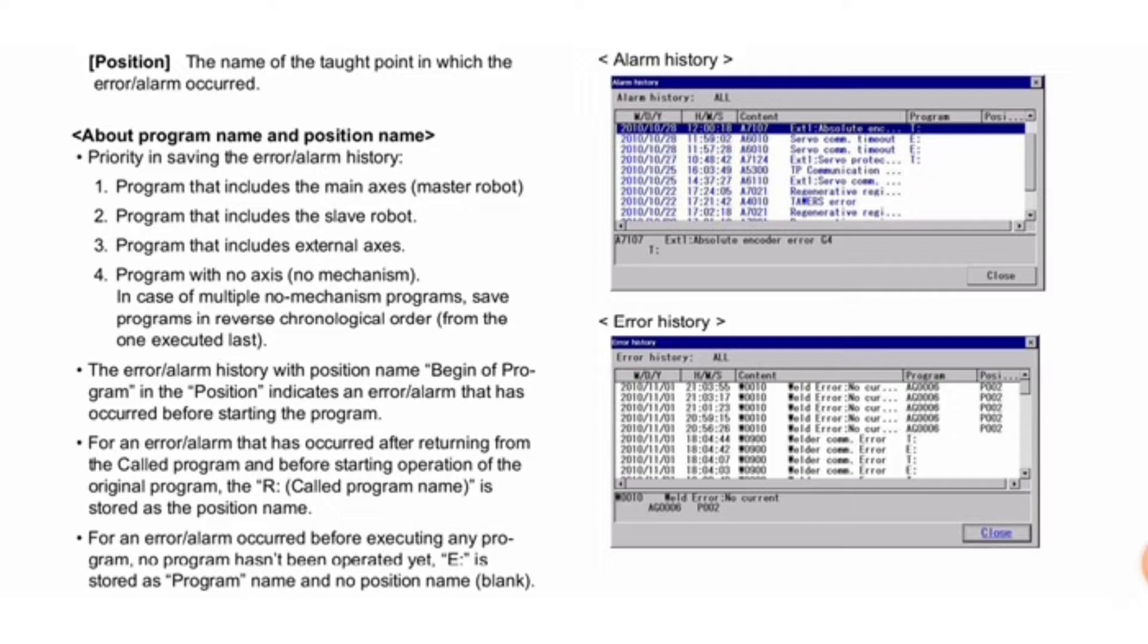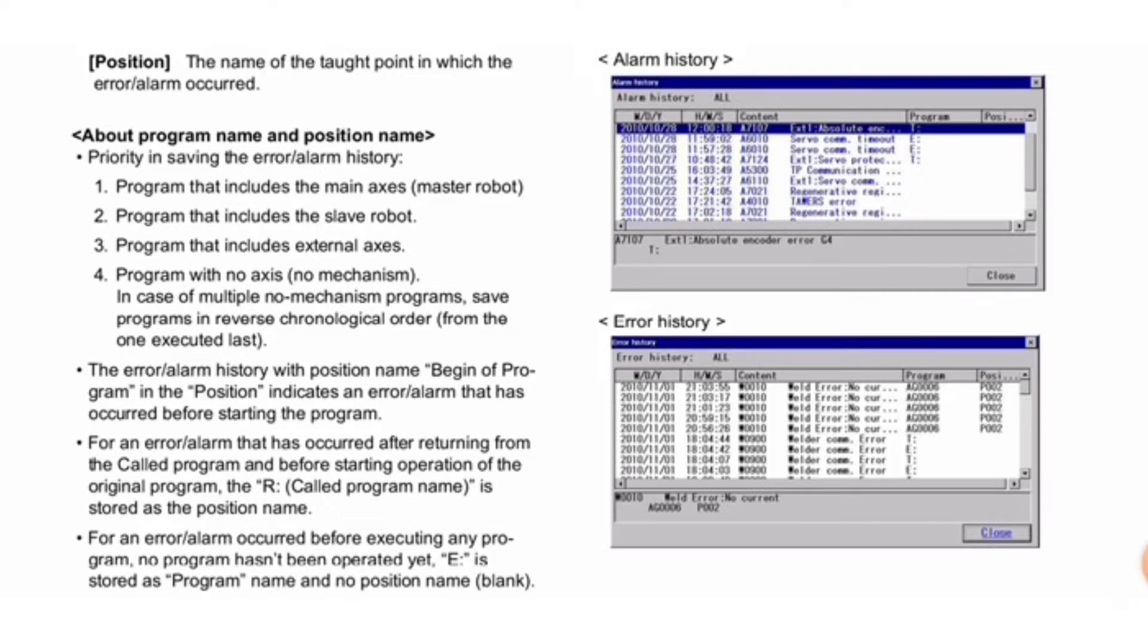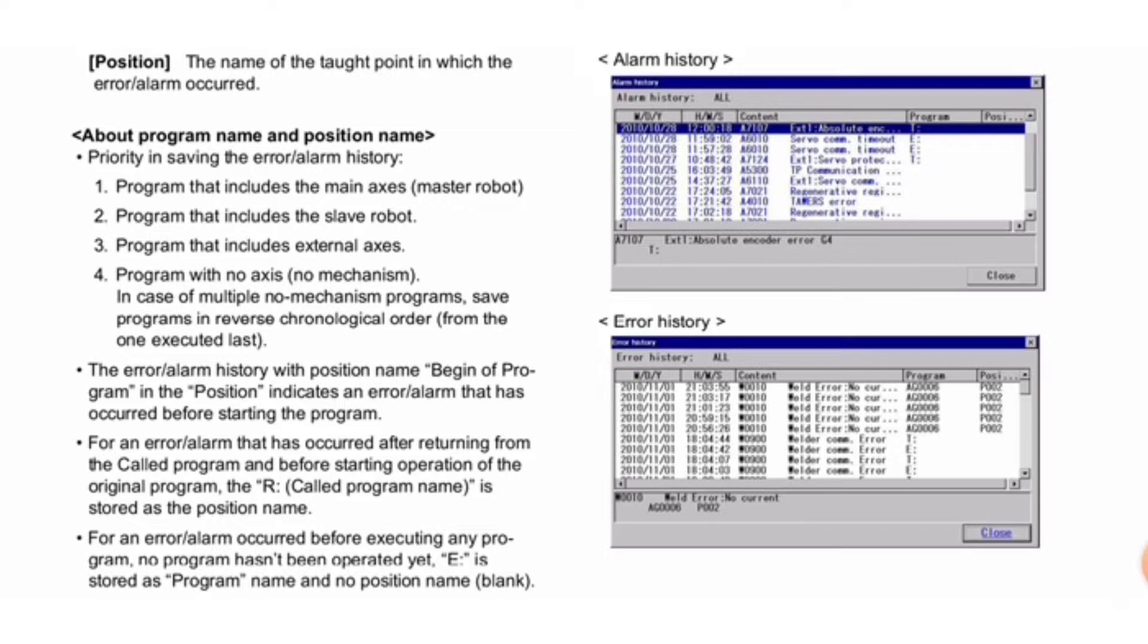The error/alarm history with position name "begin of program" indicates an error before starting the program. For errors after returning from a called program, the called program name is stored as position name. For errors before executing any program, "E" is stored as program name with no position name. All procedures can be seen in the right side image.